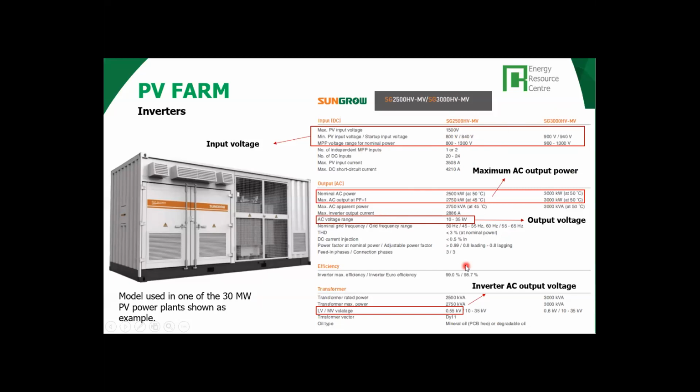Paul, it's important, the reference temperature of the power. The temperature at which this rated power is indicated will give us the maximum temperature these models can work comfortably at. So for higher temperatures than that, not probably the case in Mozambique, but it could be the case in, I don't know, some areas in the Middle East, for instance, or in the desert areas of California or Chile.